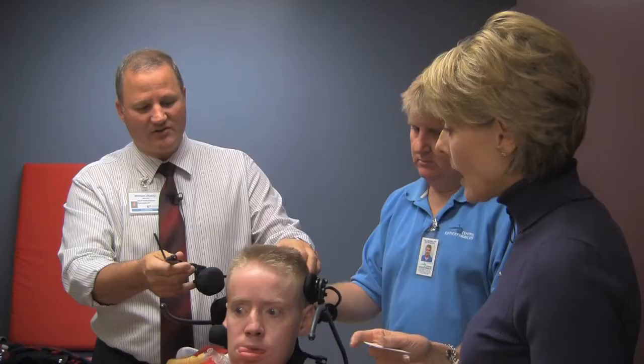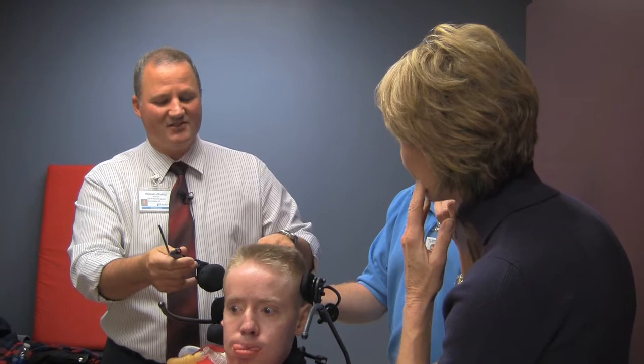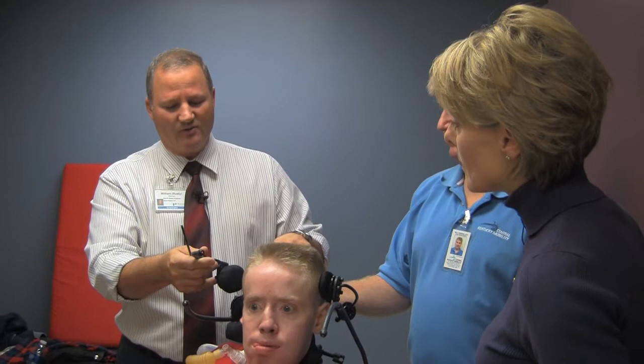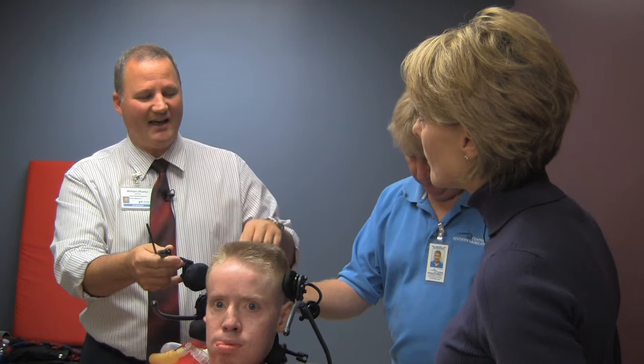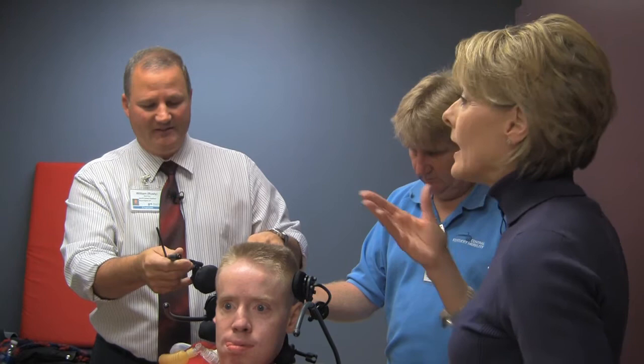He's not able to use his thumbs now, but you're going to make this work where he can use his mouth? That is correct. There are several technologies that use the mouth, but we're not really using the mouth as much as we're going to use the movement of the skin of his cheeks — by pushing his tongue against the cheek on the inside, he can actually activate the switch to make the onboard computer do what he wants it to do.